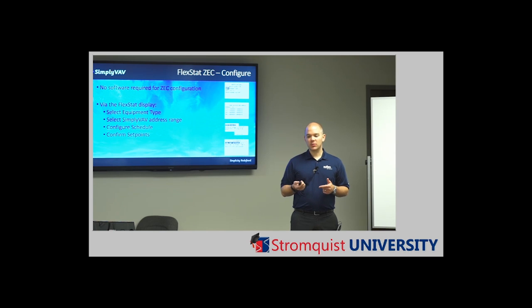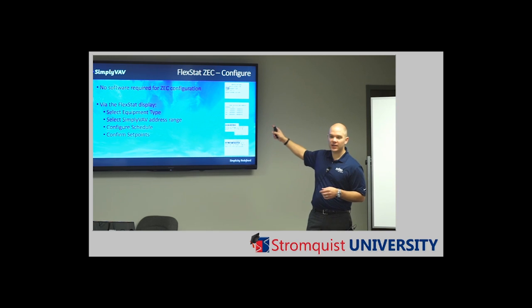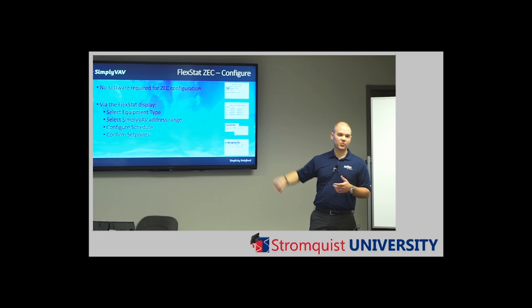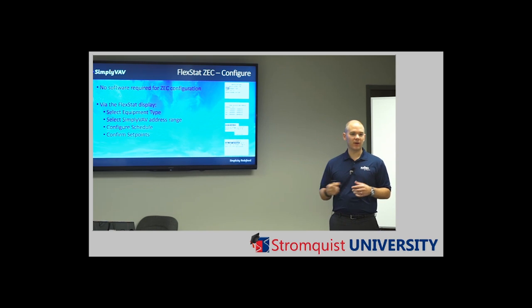Right. And we have a couple applications, like in our factory, we put one of these in the sales wing. We also have a warehouse there that's teed off that same rooftop. So we didn't want the warehouse to be in the voting of where to run the equipment because nobody's out there. We just want to maintain basic. We just addressed it outside of this range, so it gets to ride along, but it doesn't affect the control. So there's some neat applications there you can manage without having to get software out again. So out of the box, you can have 4 rooftops, 16 zones.